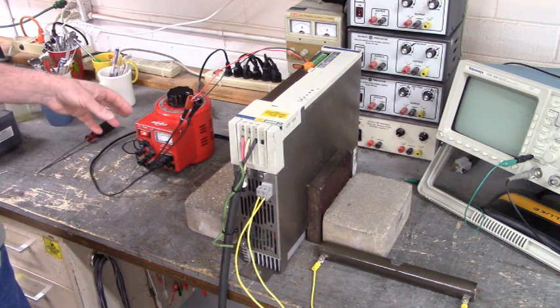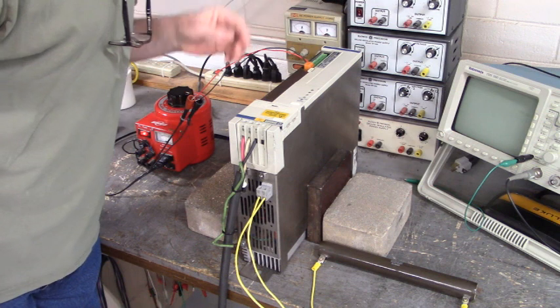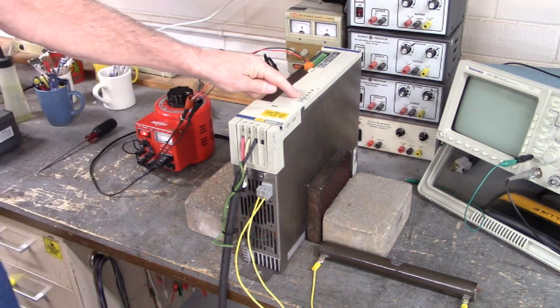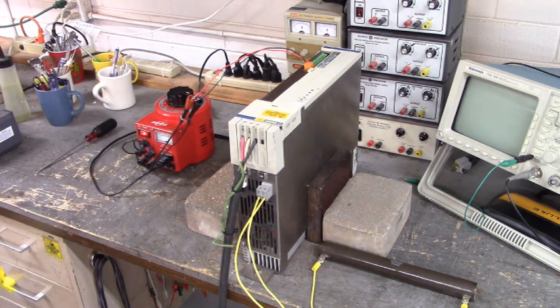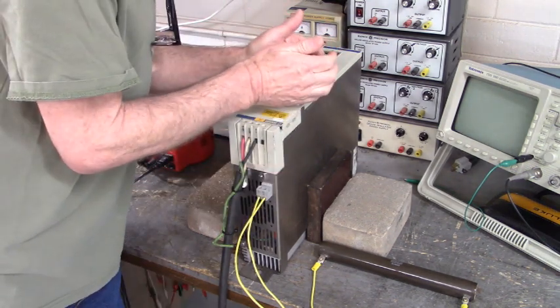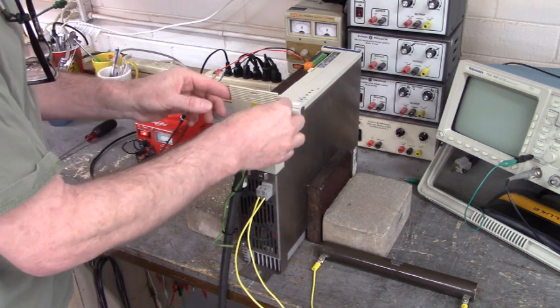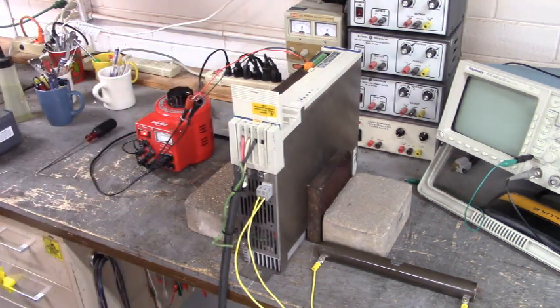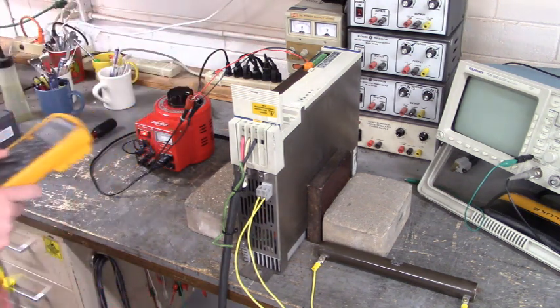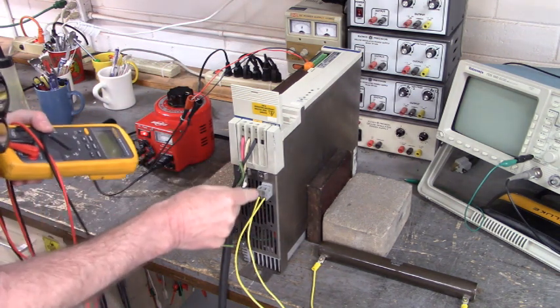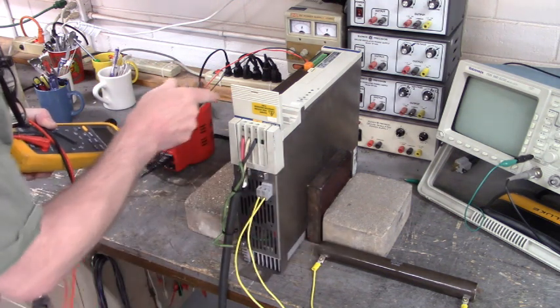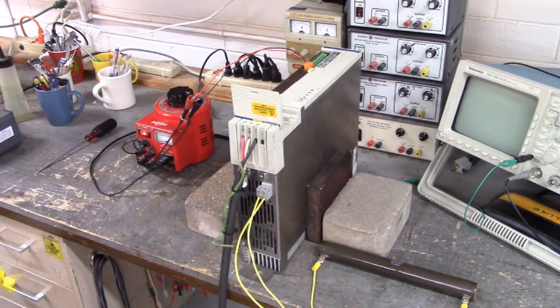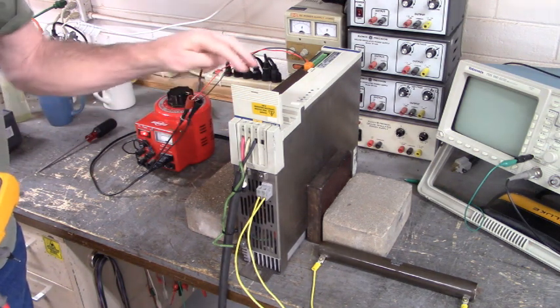Alright, we've just applied 220 volts AC single phase to pins 1 and 3 right here. The green control power LED is on. Let's apply the 380 volts AC 3 phase to L1, L2, and L3. Did you hear it energize? Let's see what we got. Alright, the green power LED is also on. Let's open up the door and we will measure our DC bus voltage at these two terminals right here. You have to have this connection to the regenerative braking resistor for that DC contactor to energize and route the voltage from the three-phase bridge out to these terminals out here.